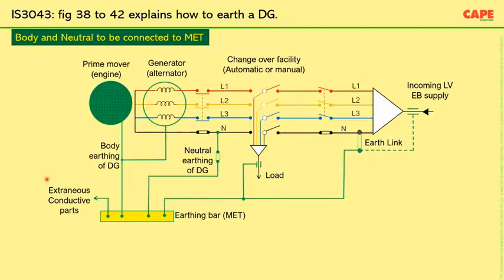The lightning protection system down conductor is running just outside the building. So the same bus bar also should be connected to the down conductor system of the lightning protection system. This also shall be connected to each and every metallic installation in the building, such as metallic water pipe, gas pipe, or whatever metallic things are there, and the metallic rebar of the building, the steel reinforcement of the building, and if you have an industrial building, the steel structure of the building. Those are called extraneous conductive parts. So a connection from MET to the extraneous conductive part is also mandatory.